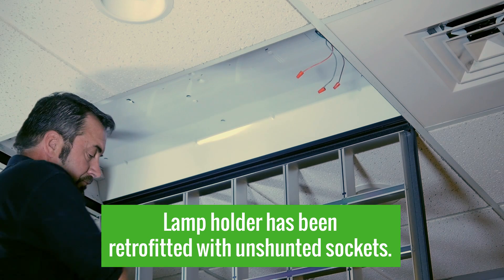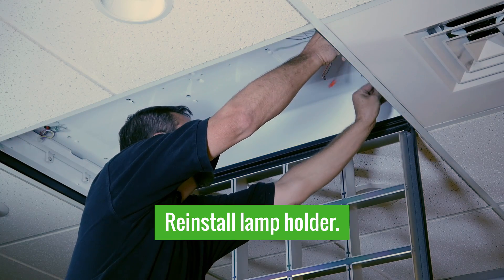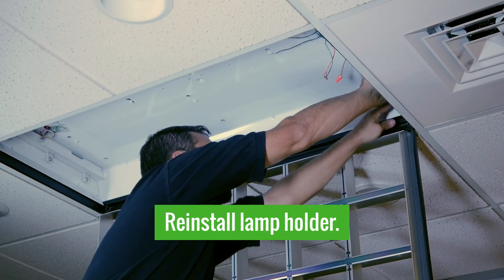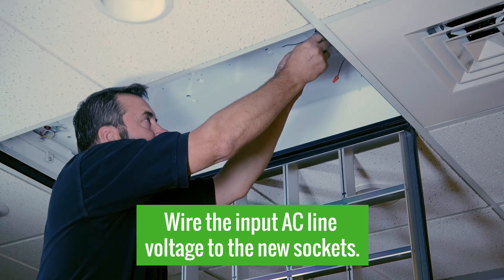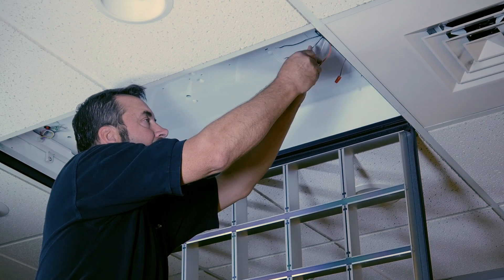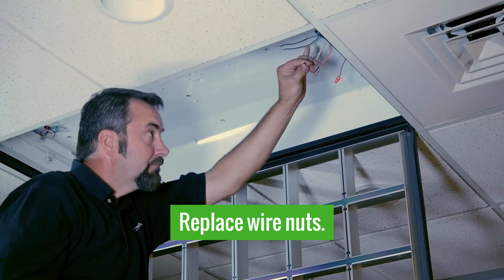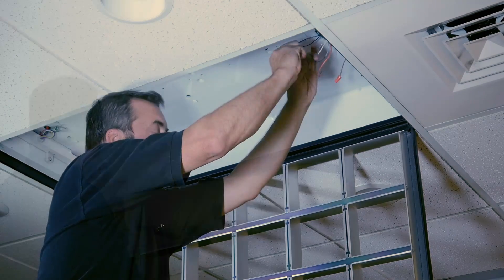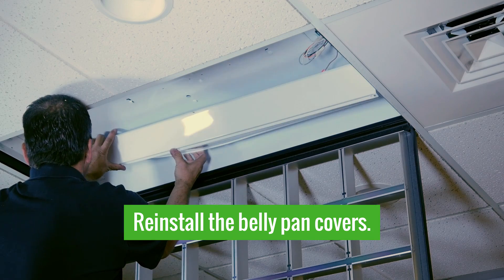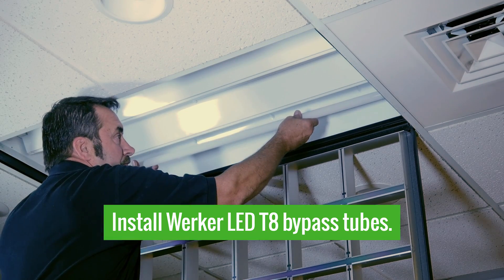We retrofitted our lamp holder bracket with the required unshunted sockets. We're going to go ahead and reinstall that into the fixture, and next we can go ahead and wire up the input AC line voltage. We'll want to use new wire nuts instead of the existing ones. And once we have those covers replaced, it's time to install our Werker LED T8 bypass tubes.